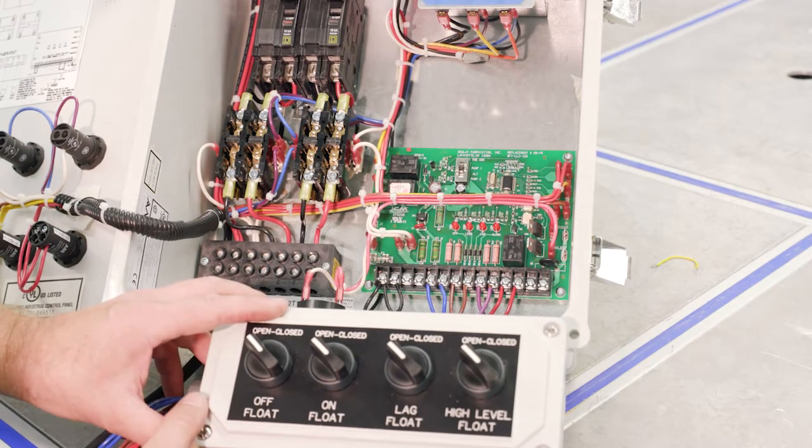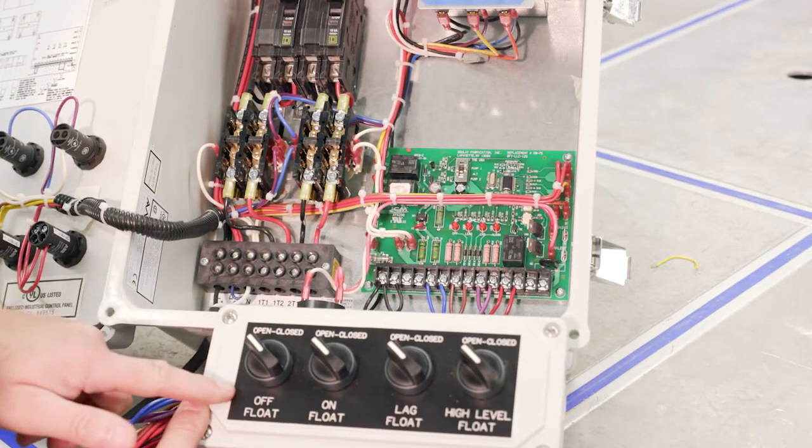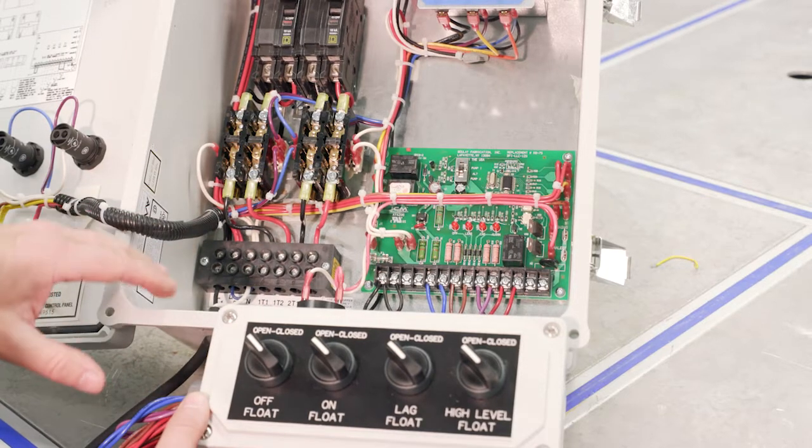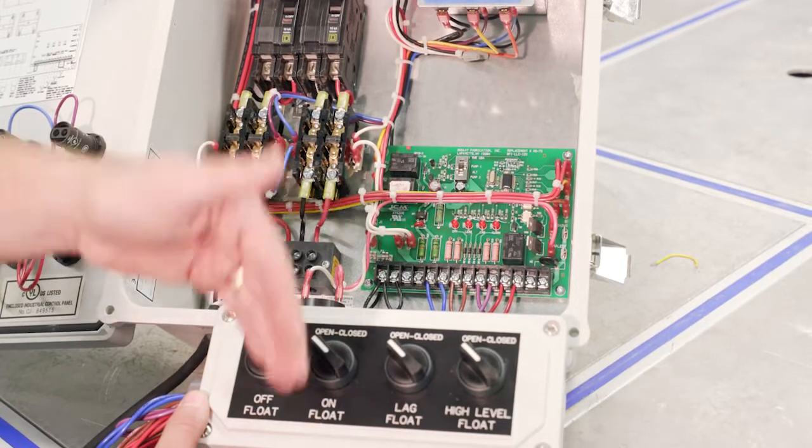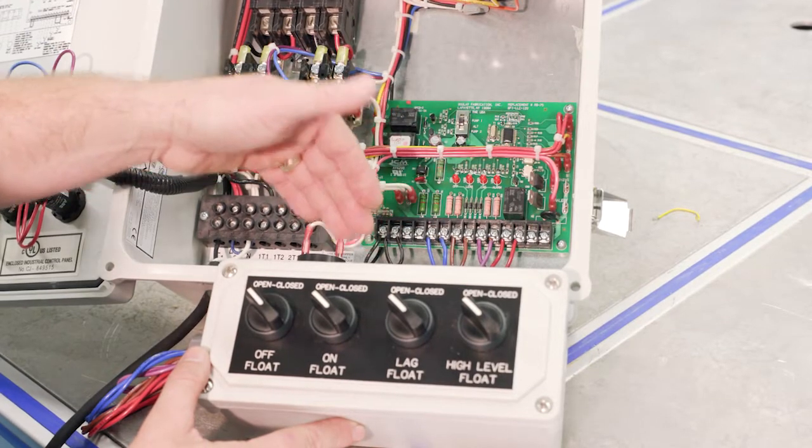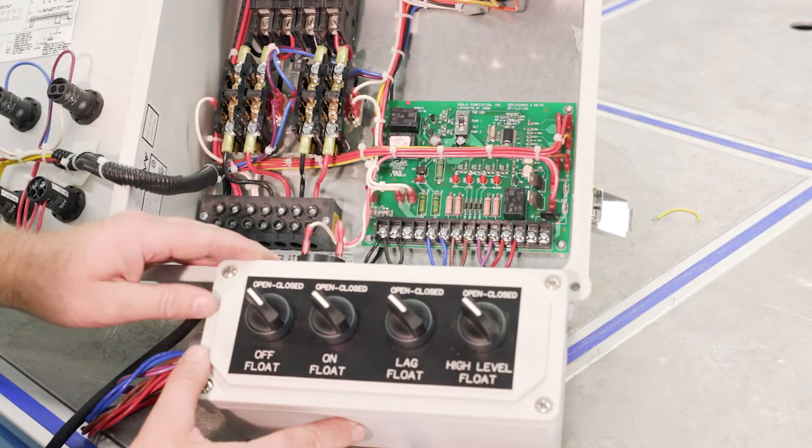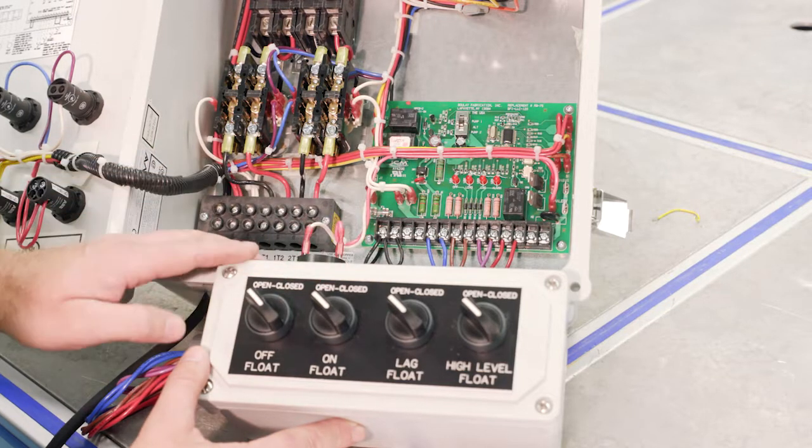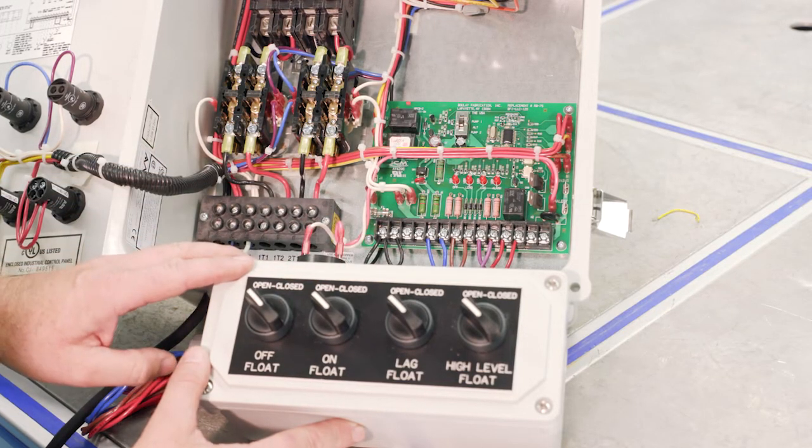So that is a typical four float system, and so if we're still having issues, then that means that there are issues with the floats in the basin because everything else is working out here, and the switches are working like they're supposed to work.